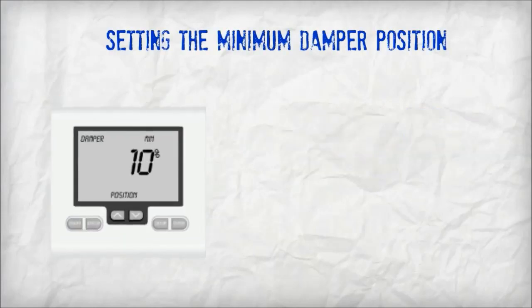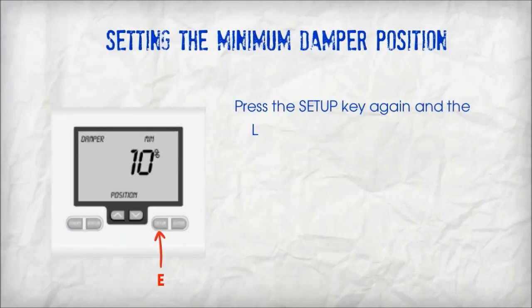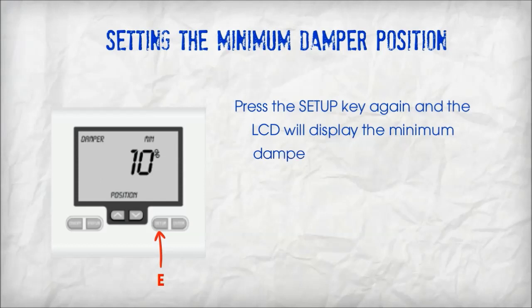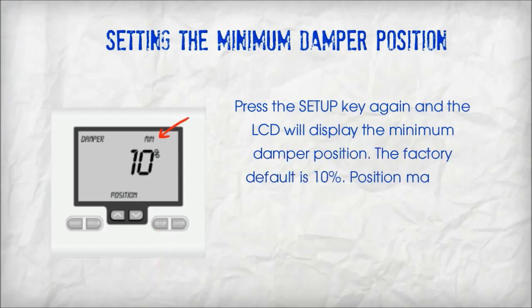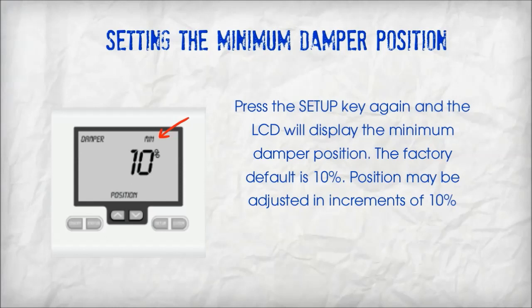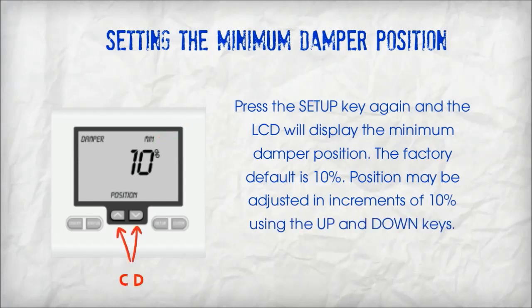Setting the minimum damper position. Press the setup key again and the LCD will display the minimum damper position. The factory default is 10%. Position may be adjusted in increments of 10% using the up and down keys.